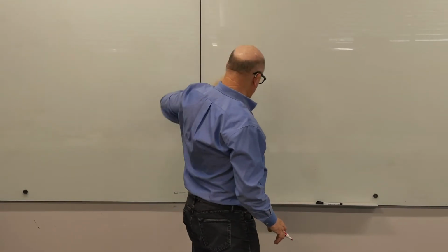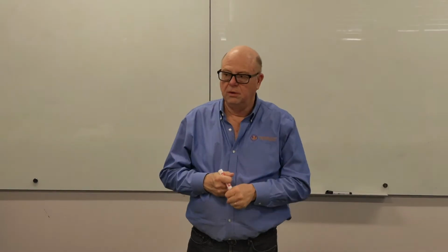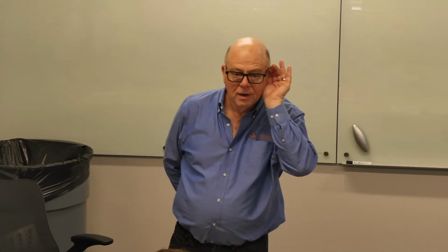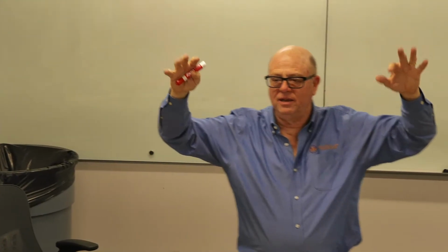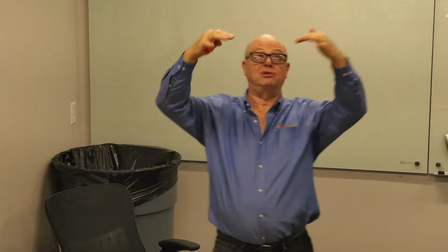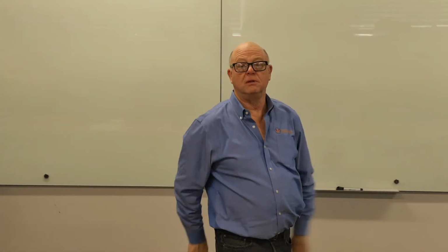So that was our little conversation about return air. Now, if I use the term open ceiling return, what does that mean to you guys? Well, open ceiling return, okay, no duct. No return duct. What if I say open ceiling supply? That means there's no ceiling. Now, if there's no ceiling, and you can see the supply duct up there, what's different than if you actually had a ceiling? Give me some differences, because there's several.